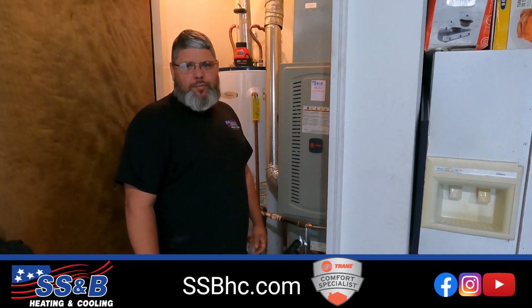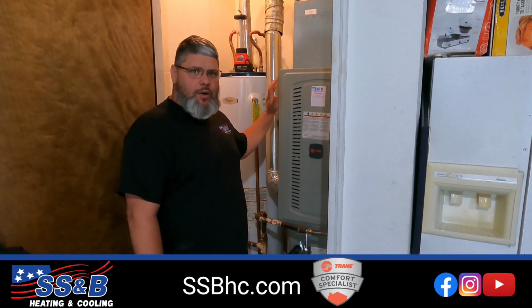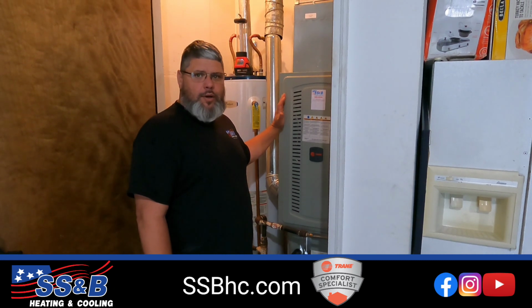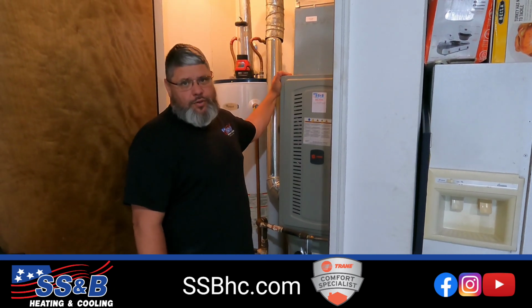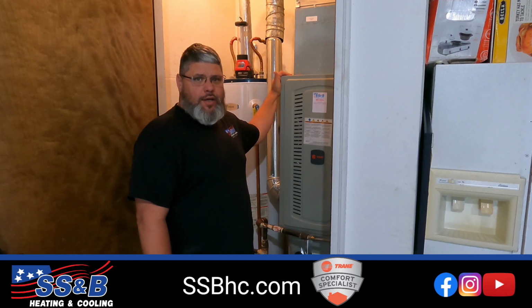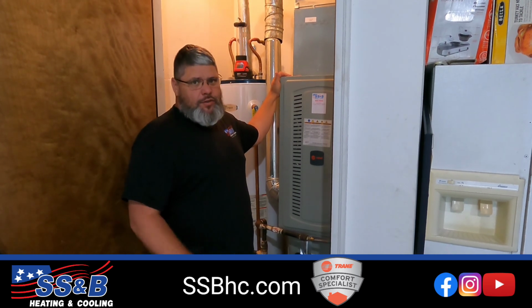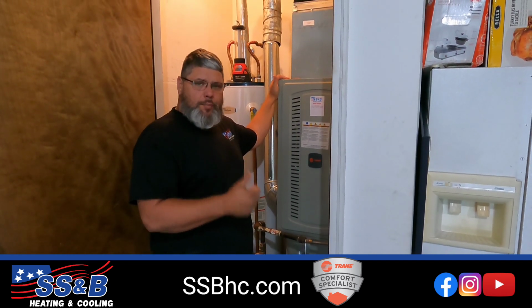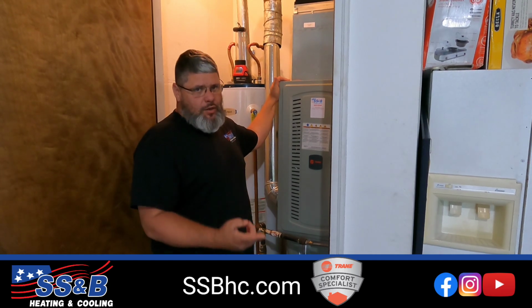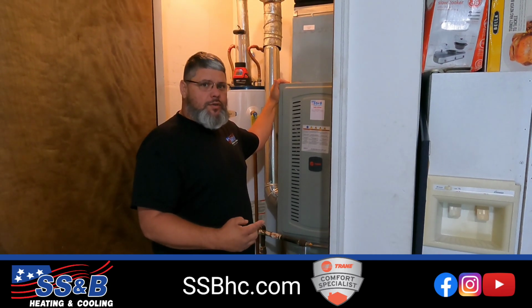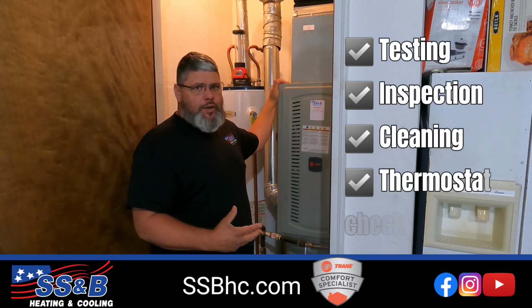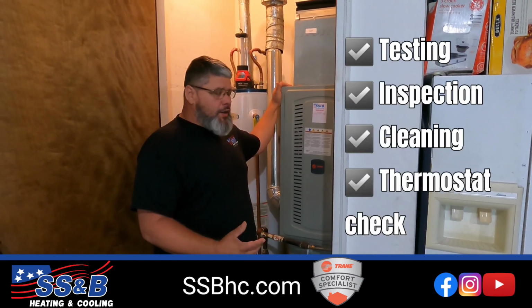Hello, I'm Charles with SS&B, and today what I'd like to show you is how we do our maintenance for our maintenance program. This is a gas furnace, so we're going to be doing the heating service today. Part of our heating service is to make sure that we check operation of the system based off what the manufacturer wants that system to do. So there's a lot of checks that we do that a lot of customers won't see.